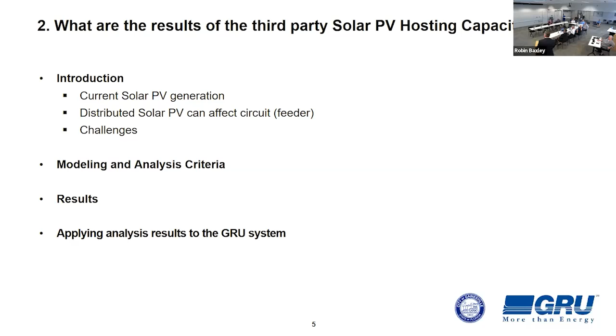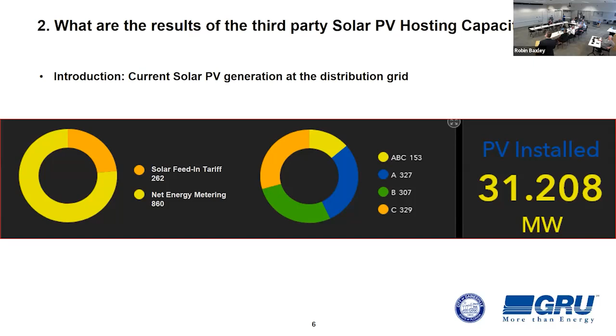Looking at the total solar PV connected to GRU's distribution system, the total at the time of the study was 31.208 megawatts. On the left side of the slide we show the number of connected customers: 262 customers are connected via the solar feed-in tariff, and 860 additional customers are connected using the net metering or net energy metering contract. The middle portion shows the number of customers connected per phase, A, B, and C, and the top part, ABC, shows the number of three-phase solar PV generators connected, which is 153.